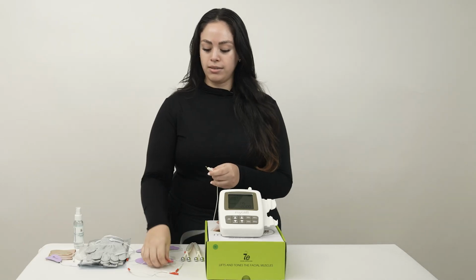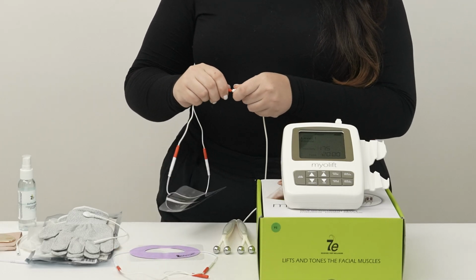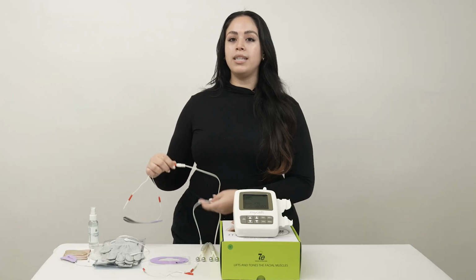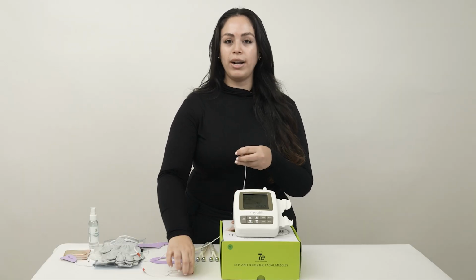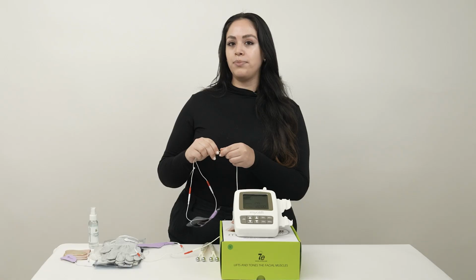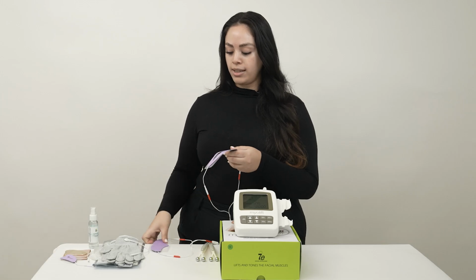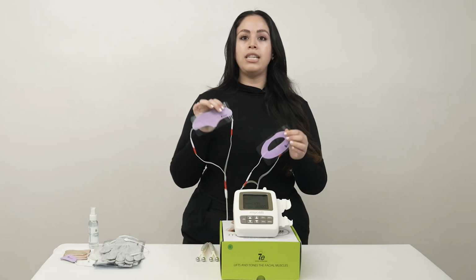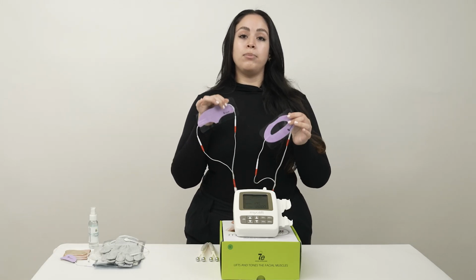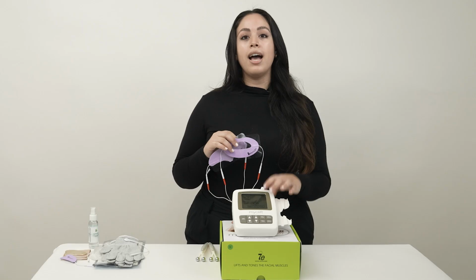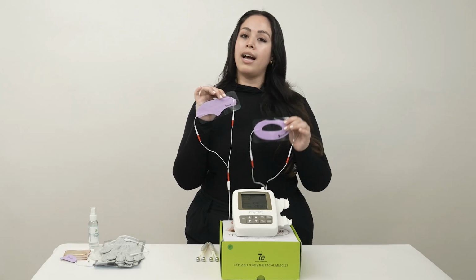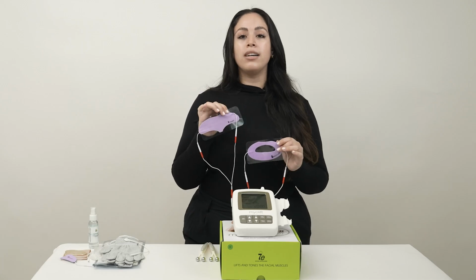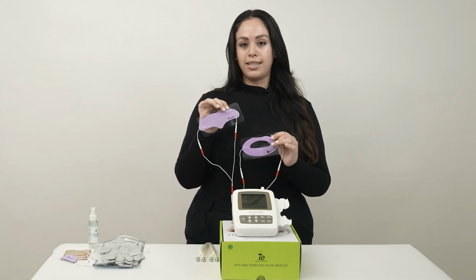Starting with the mask, once you have plugged the mask into the lead wire, you are ready to apply it to hydrated skin. Please note that no conductivity gel is needed when using the mask. When using two mask attachments, please know that the intensity is split between the two. For example, if the intensity on your device is set at 400 and you have the forehead mask and the mouth mask on, each mask will be conducting at 200 intensity.